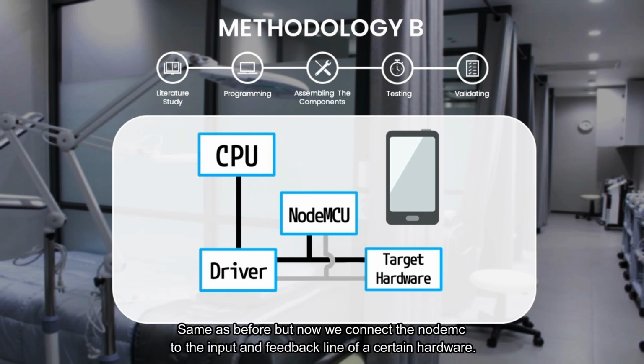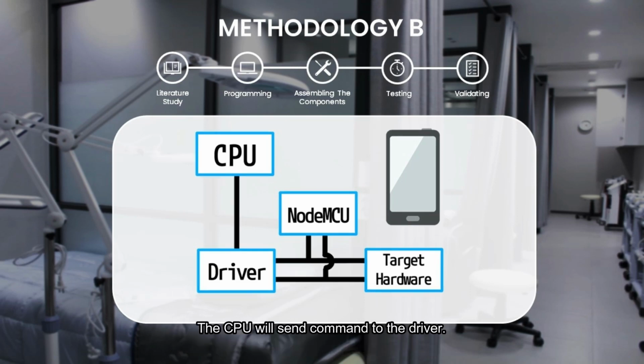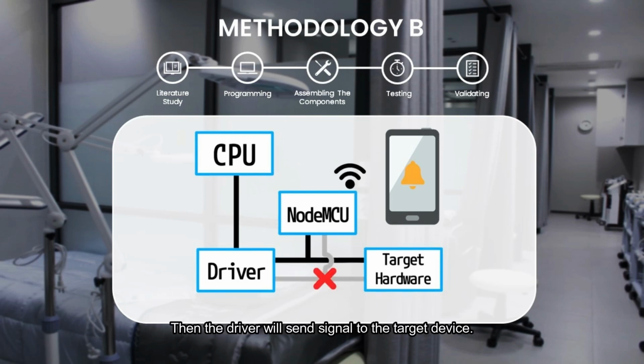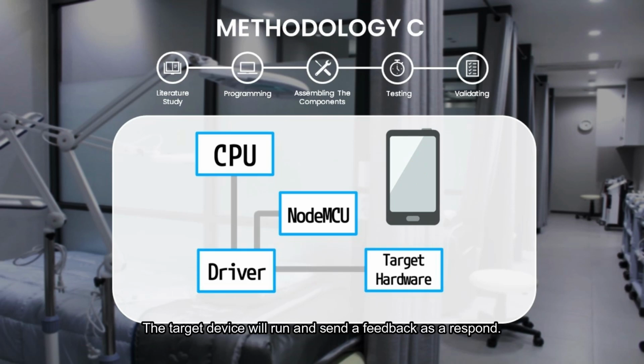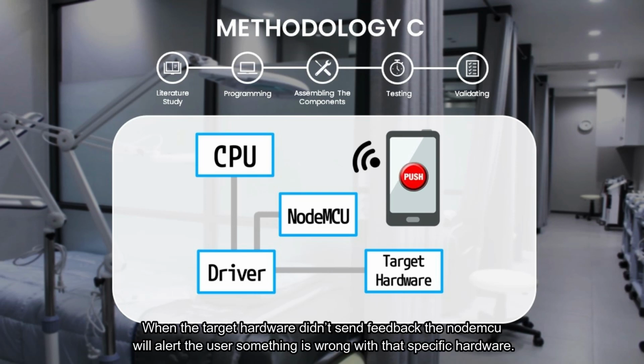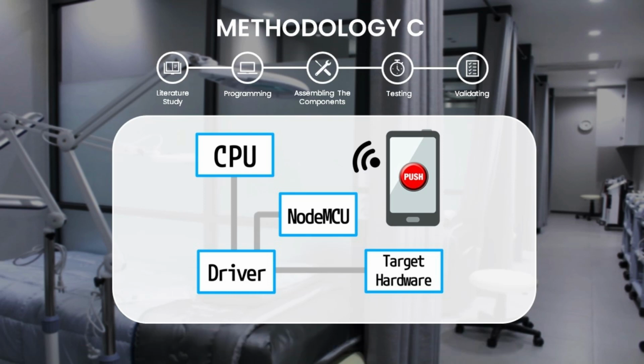Same as before, but now we connect the NodeMCU to the input and feedback line of a certain hardware. The CPU will send a command to the driver. Then the driver will send a signal to the target device. The target device will run and send feedback as a response. When the target hardware doesn't send feedback, the NodeMCU will alert the user something is wrong with that specific hardware. This time, connect the NodeMCU to the driver.